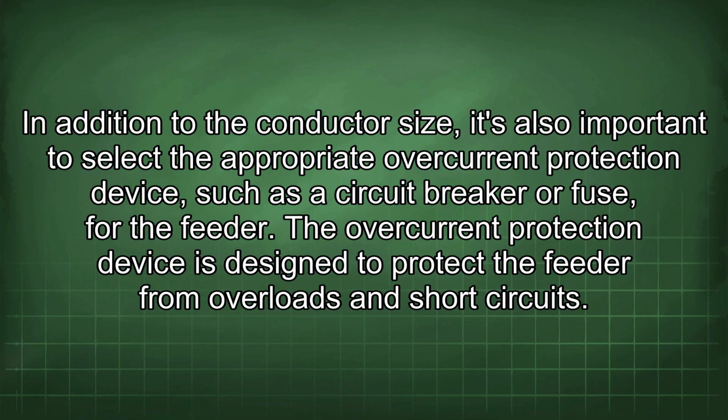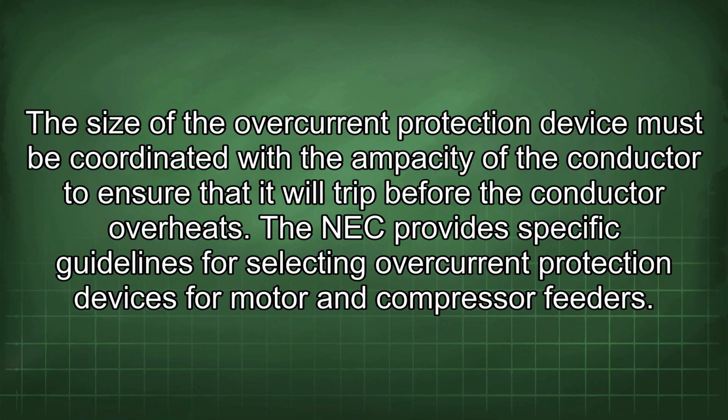In addition to the conductor size, it's also important to select the appropriate overcurrent protection device, such as a circuit breaker or fuse, for the feeder. The overcurrent protection device is designed to protect the feeder from overloads and short circuits. The size of the overcurrent protection device must be coordinated with the ampacity of the conductor to ensure that it will trip before the conductor overheats.